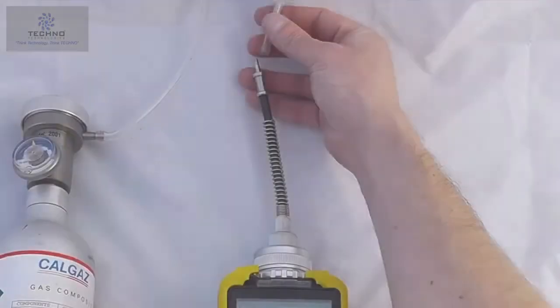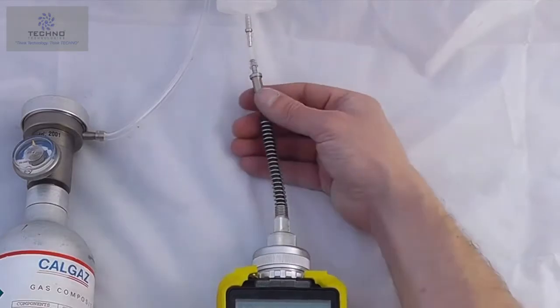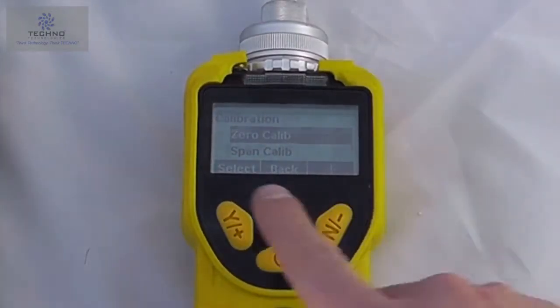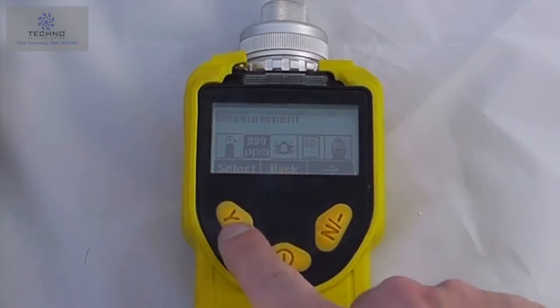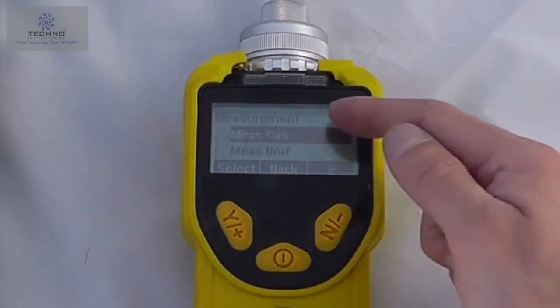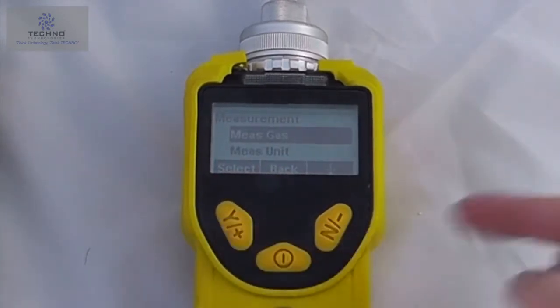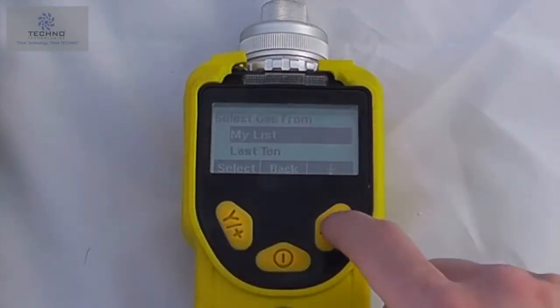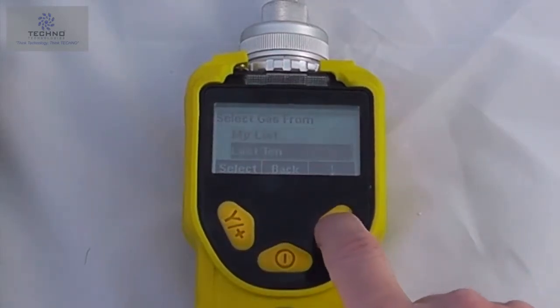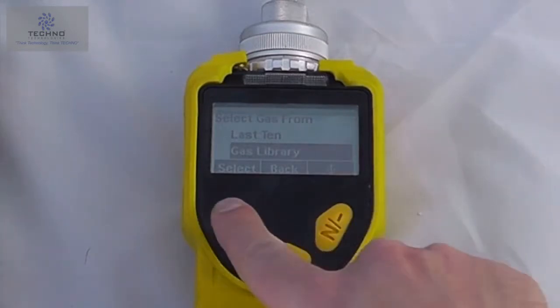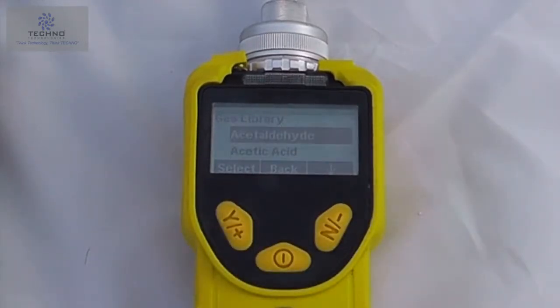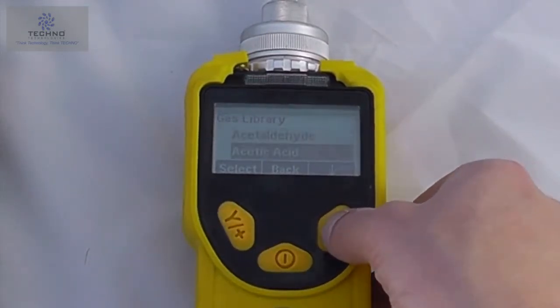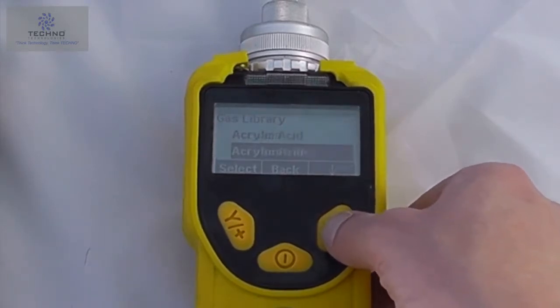So to look at the menus in a bit more detail, I'll reapply the hydrophobic filter to the end of the instrument. If we go back, we also get the option for measurement settings, so looking at things like our measurement gas. So if we select that, we can see from my existing list, my last 10 gases used, or the total gas library. So to skip into the gas library, this also means you can input any preset correction factors for any gases you may want to measure.